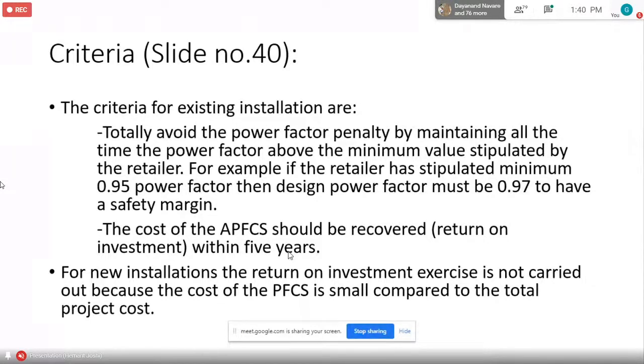Cost of the power factor correction should be recovered within 5 years. Return on investment. There is a standard formula for return on investment. You put the numbers in that and you see whether you can get it in 5 years. Otherwise, it's not really worthwhile. You may have to check whether it is better to pay the penalty. But it's a balance between this.